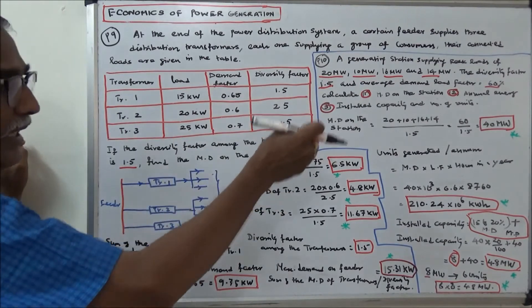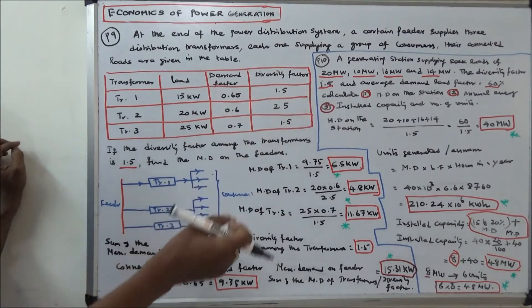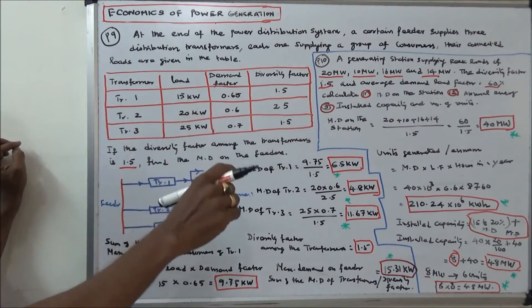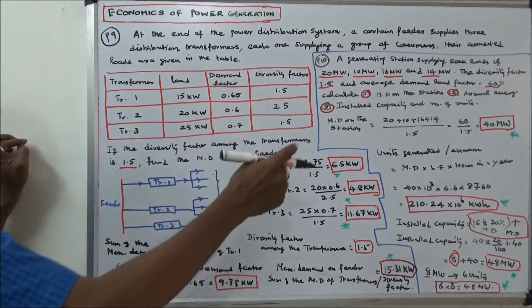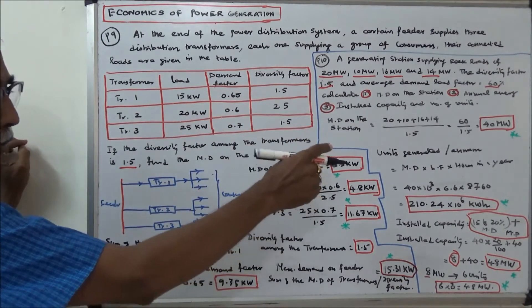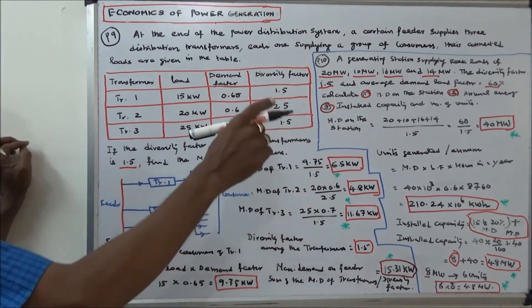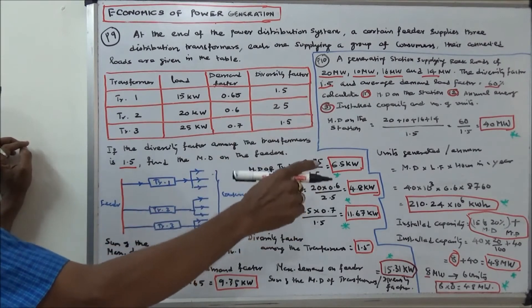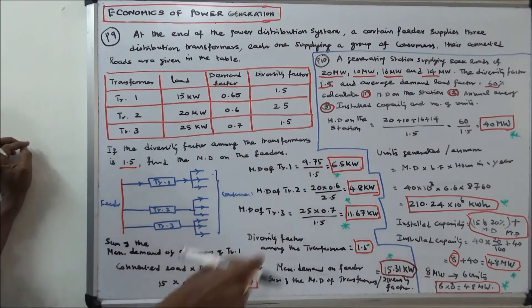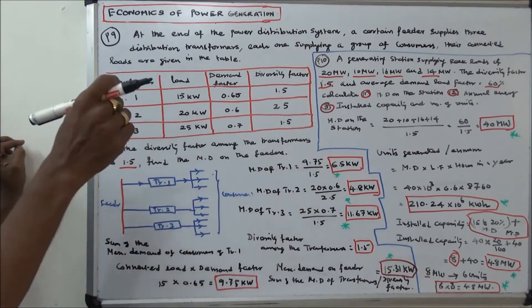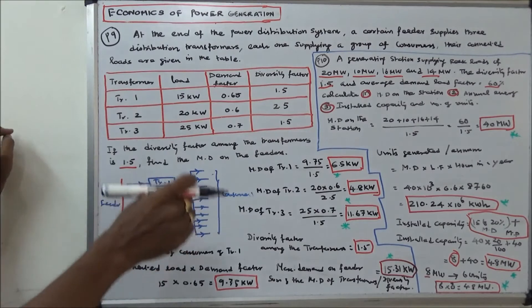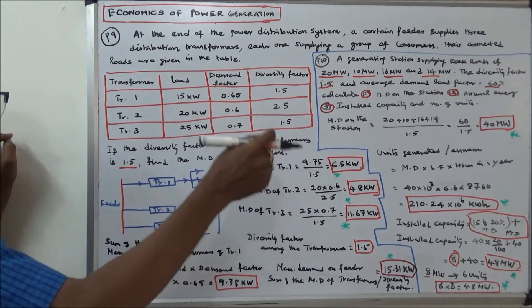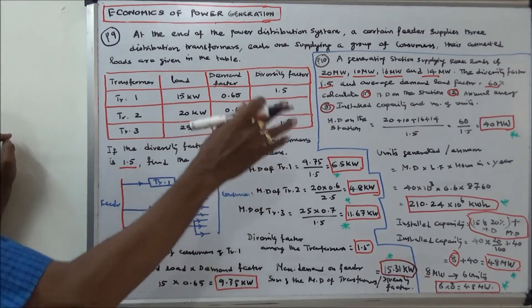Number two: units generated per annum equals maximum demand multiplied by load factor multiplied by hours in a year. Maximum demand is 40 megawatts, load factor is 0.6, and hours in a year is 8760. The units generated per annum by the generating station is 210.24 × 10⁶ kilowatt-hours.